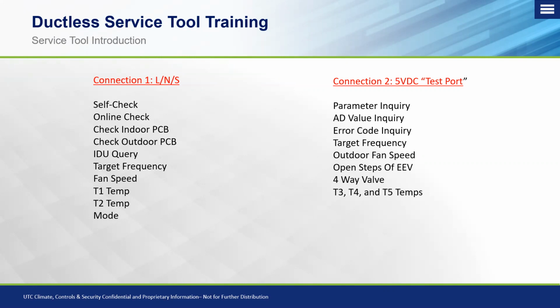The second connection, which plugs into your outdoor unit on the 5-volt connection, is the test port pin on the board. Typically, they're a red color. I have seen them in white as well, but what you're looking for is a test port connection. So with that, you're getting your parameter inquiry, the AD value inquiry, error codes, target frequency of the compressor, outdoor fan speed, the opening steps or the pulses of the EEV, the 4-way valve position, T3, T4, T5 temperatures, as well as your T2B temperatures, which we know is that average for those EXVs to maintain, and also the threshold on where it opens a valve or closes a valve based on that average.